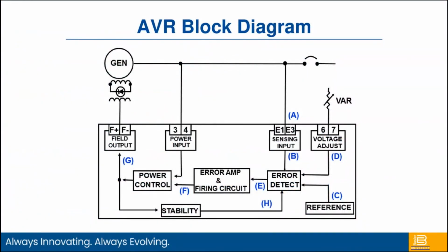To start off, I just want to discuss what a voltage regulator is. The whole purpose of a voltage regulator is to regulate the generator voltage. It's looking at the output of the generator at its terminals, and the voltage regulator looks at where its set point is versus what the output of the generator is and makes corrections. It does this by applying a DC flux to the field of that particular machine. By increasing the amount of excitation to the generator field, we can increase the output of the generator, or the voltage output.